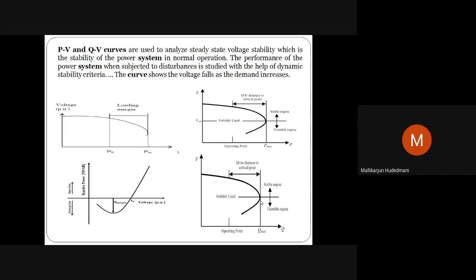and at a certain point later, the reactive power flowing or being absorbed by the loads seriously affects the voltage profile of the system, causing voltage collapse. Now I am in a good position to tell you what is voltage collapse. Voltage collapse is a very serious, dangerous phenomenon noticed in power system operation, wherein there is a serious fall of voltage due to rapid drawal of active and reactive power up to a certain critical point, and later it is not possible for the system to cope with that. What will happen at that critical point? Suddenly a massive fall of voltage is observed. Therefore voltage collapse is a very serious phenomenon. After a certain point, stability of the system is lost, so voltage comes very drastically to a lower point. That in turn will seriously affect the rest of the connected system.